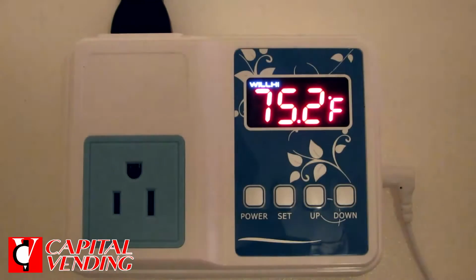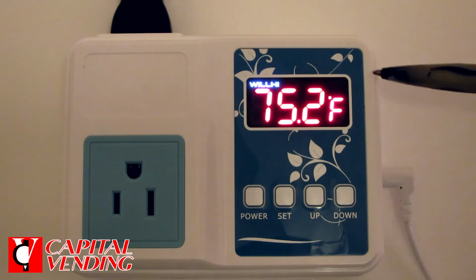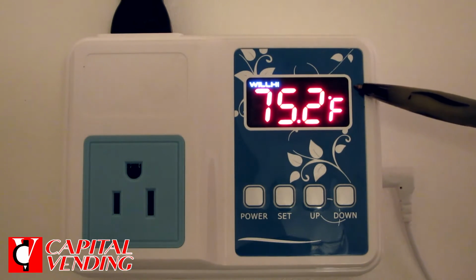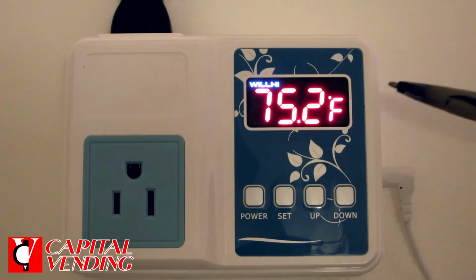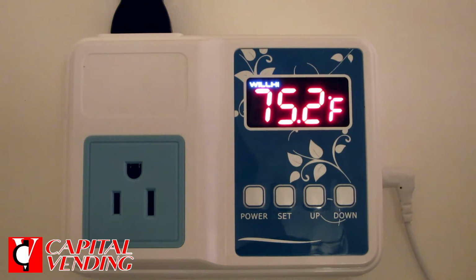Here's an overview of our universal refrigeration controller, and I want to show you some things. Right now it's very important that this 'working' indicator is blinking — while it's blinking, it won't activate your refrigeration system. When we send this to you, we put in a 15-minute time delay, just to prevent hard starts and keep your refrigeration system in good shape.